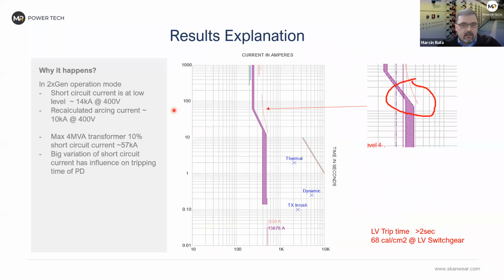So to give you background on why we have 68 calories in this specific location, I have to just point you to the time current curves. This is a low voltage breaker tripping curve. That was medium voltage, just for this specific scenario. And from 2 generators, what we expected to see initially was approximately 14 kiloamps. And if we recalculate it back to the arc current, it will be something around 10 for this specific project.